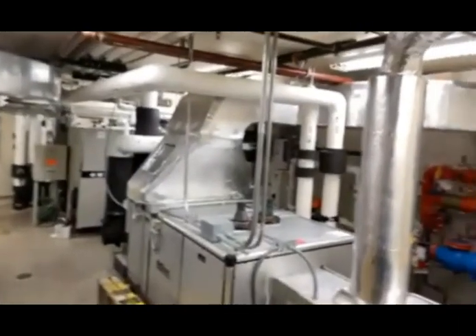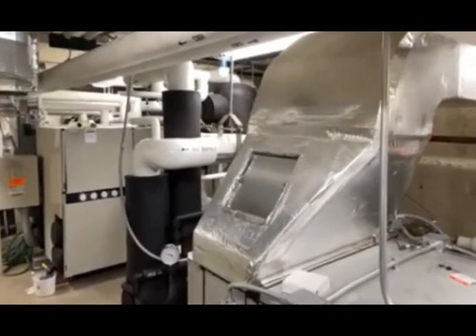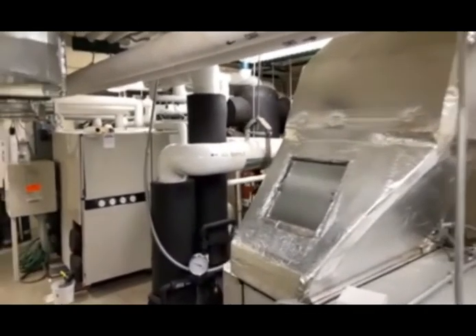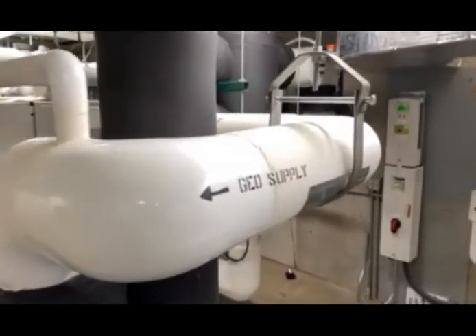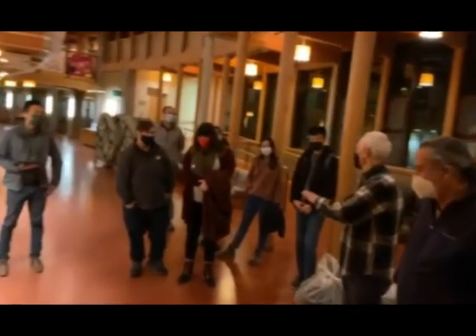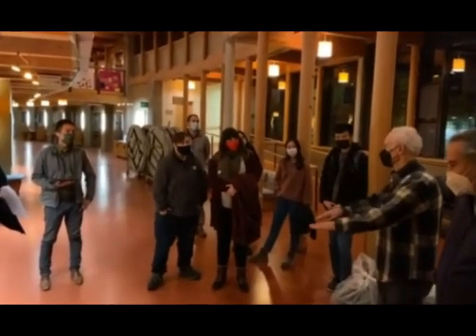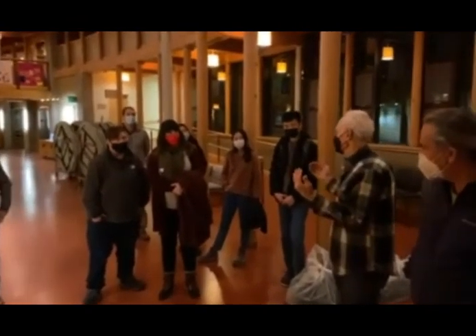Does everybody know the history of the original building? There's 10,000 feet of hydronic heating in the floor of the original building completed in like 1950. Frank Lloyd Wright liked hydronic heating. So for every square foot up there, there's a foot of welded piping, where there's like five zones and all these arrays made up with no insulation on them. If you open up the cement, which we've done rather than leaks, you'll just see crushed stone, and the piping was laid on top of it and the cement poured on top of that. So each pipe is there with cement only covering about half of it.